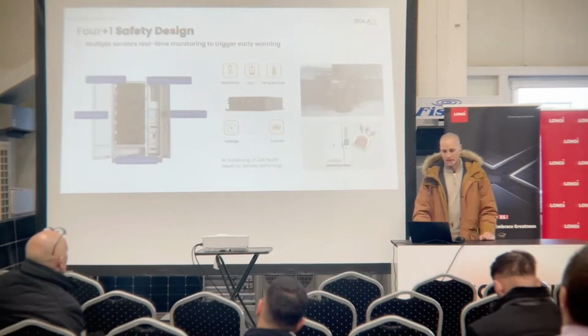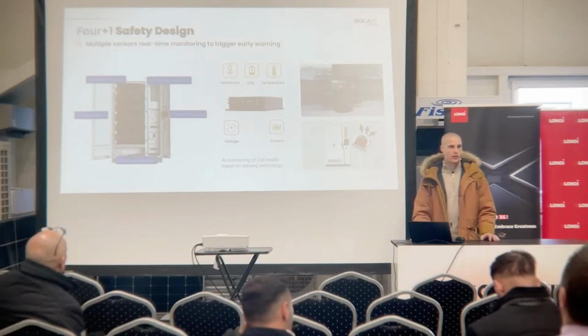Okay, this is still about the DC coupled solution. Basically, if you use a 50 kilowatt hybrid inverter with the battery, you can install 100 kilowatt peak DC capacity for the inverter, and you can use 50 kilowatt to charge the batteries and 50 kilowatt to feed back to the grid. So it's a 50 kilowatt inverter, but you can utilize 100 kilowatt because of the 200% oversizing for the DC side.